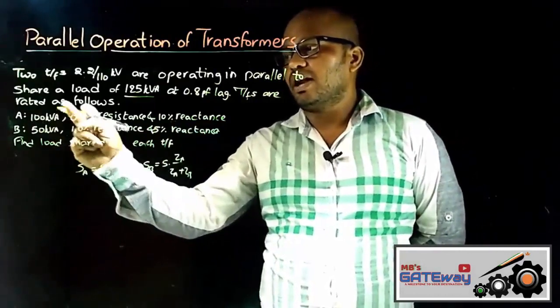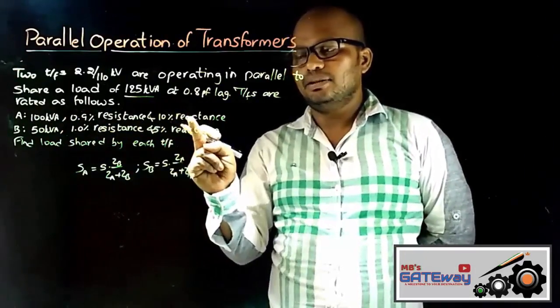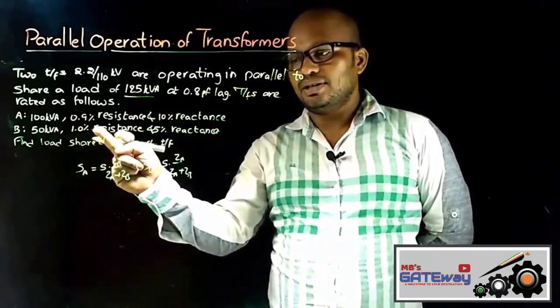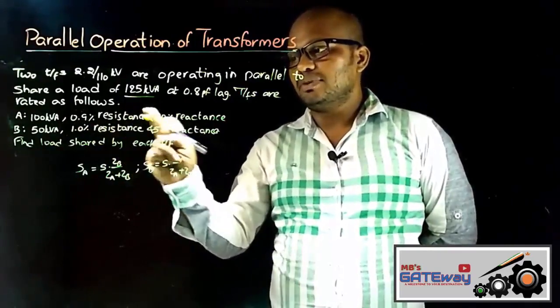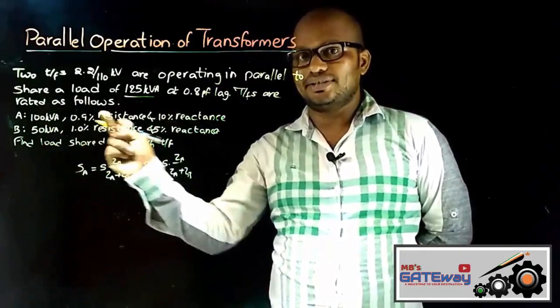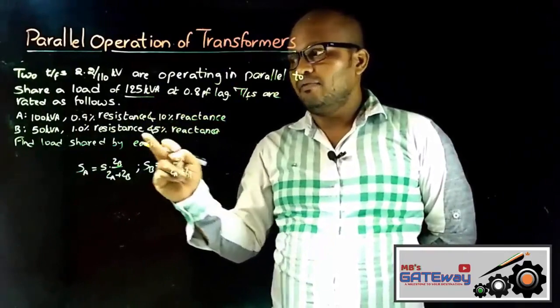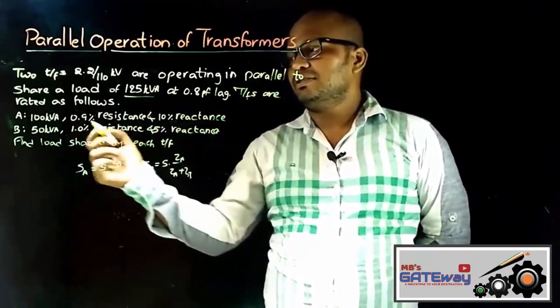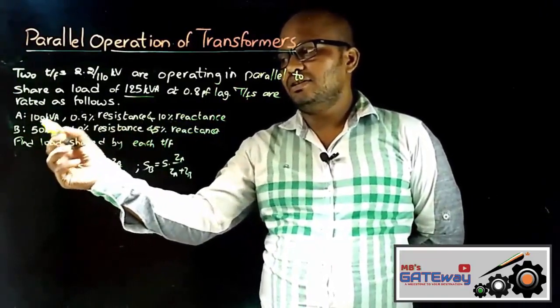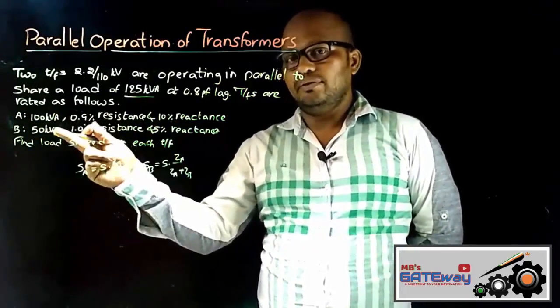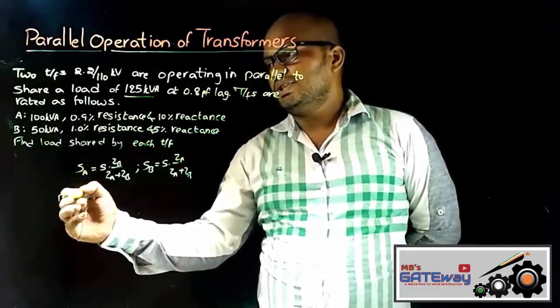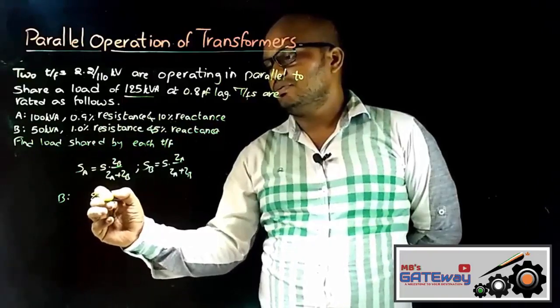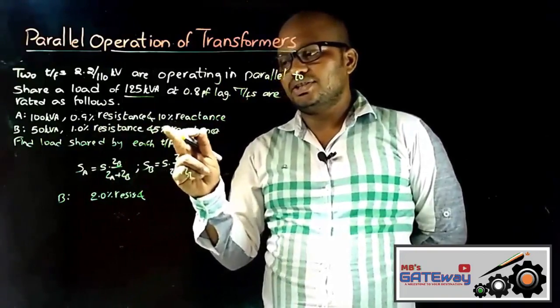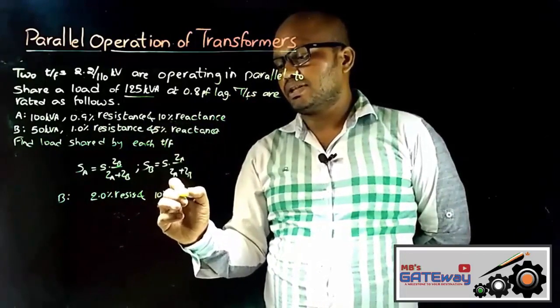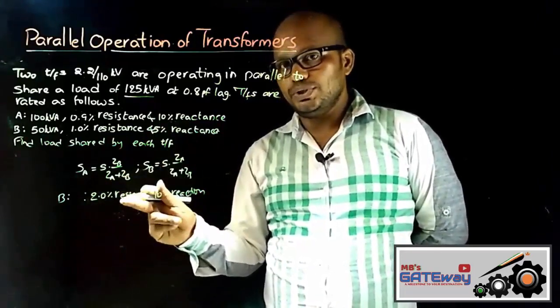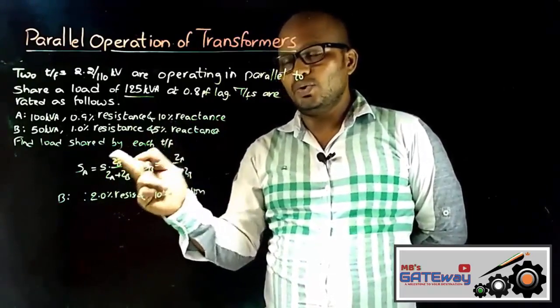And observe that here for 100 kVA these are the corresponding percentage resistance and percentage reactance, and for 50 kVA this is the percentage resistance and this is the percentage reactance. Means these resistance and reactance values correspond to different ratings. And for solving this numerical problem we must adjust these values to the same rating. That is, keep 100 kVA as it is, and let's adjust the 50 kVA to 100 kVA. Means 50 kVA becomes 100 kVA by multiplying with 2. So by adjusting to the same rating, resistance value changes to 2.0 percent and reactance changes to 2 into 5, means 10 percent reactance. So now we must use these values here to find the load shared by each transformer.